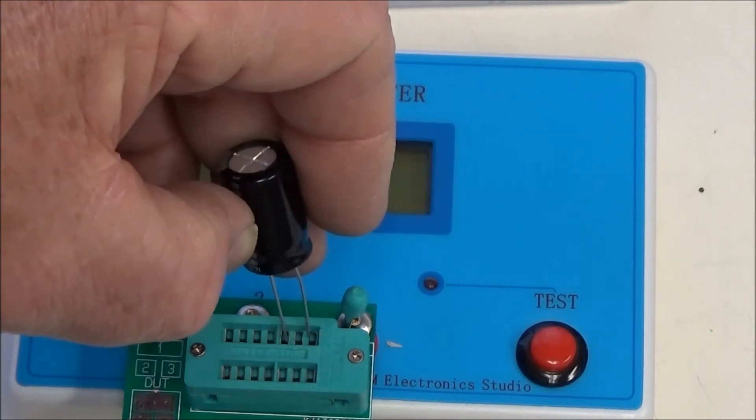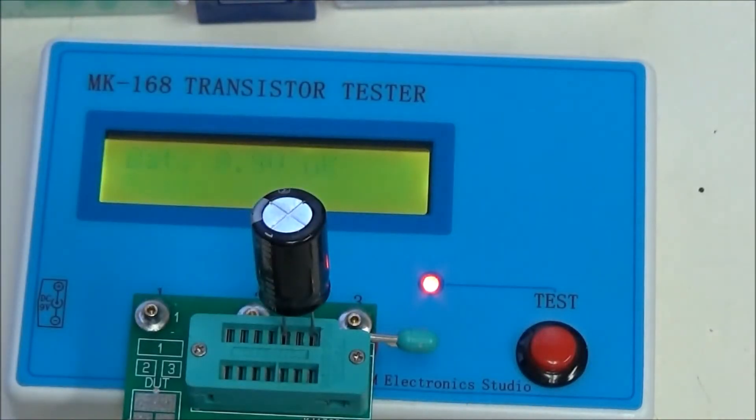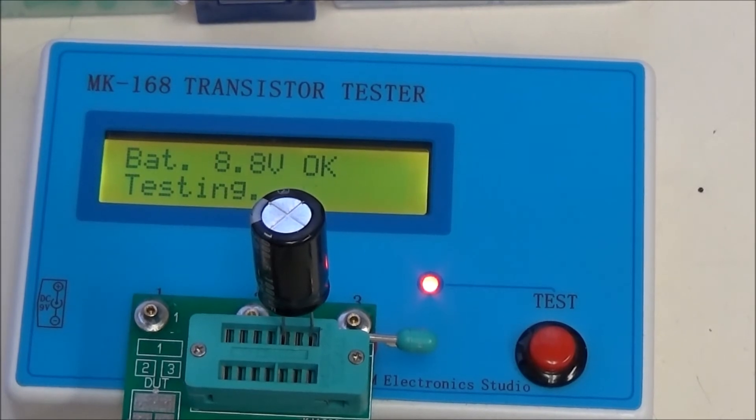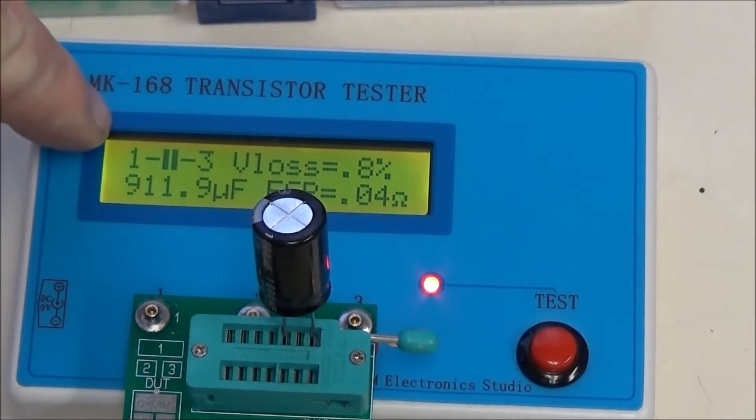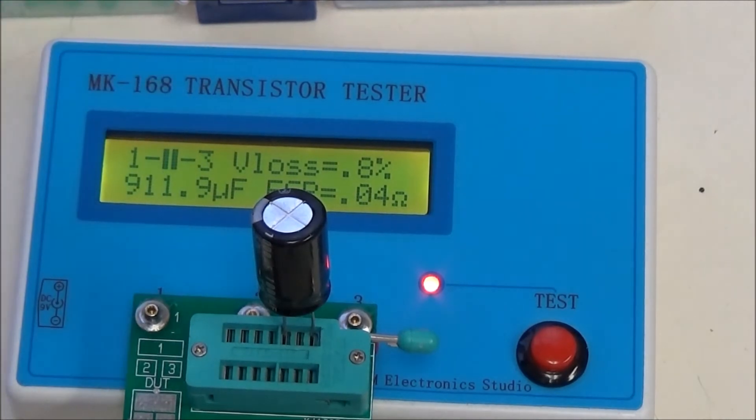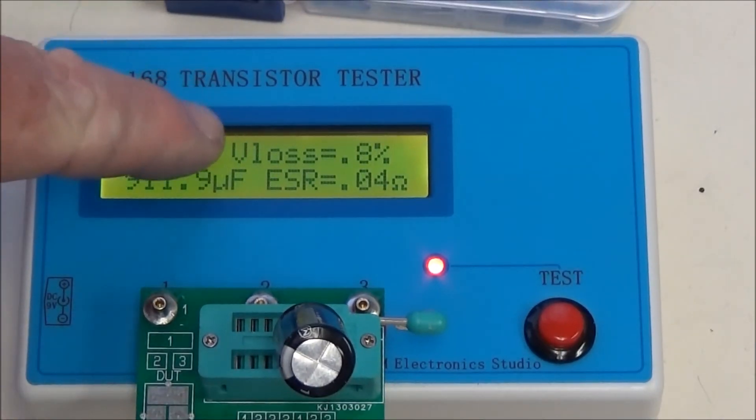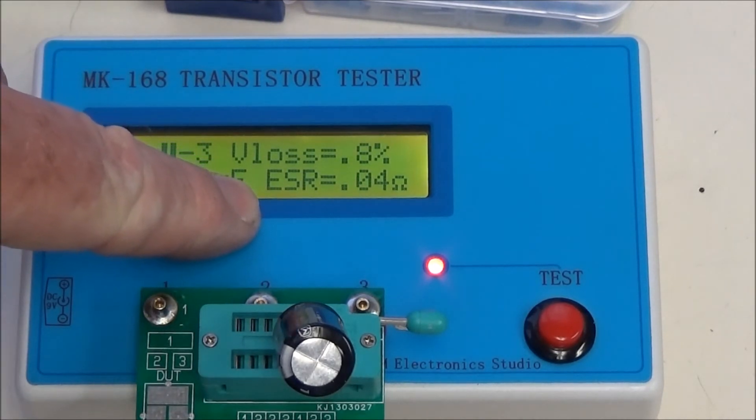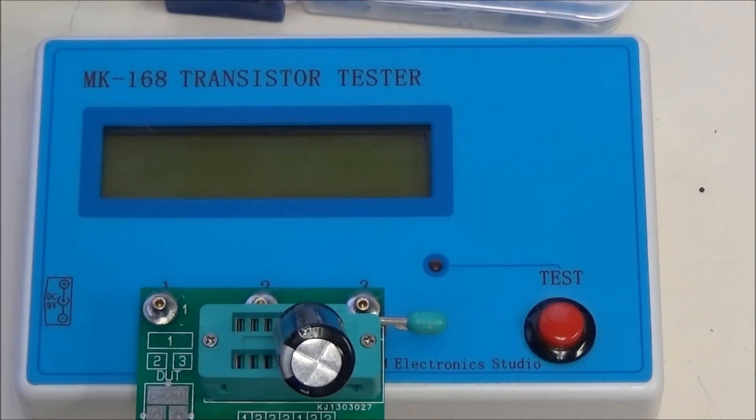This is one that I bought new. Let's see how it does. All right, 911 microfarads. It's rated at a thousand, that's within specs. It tells you that it's connected to 1 and 3. But notice loss - that's losses through the electrolyte, through the plates and whatever. But this is something you need to note: ESR equals 0.04 ohms.